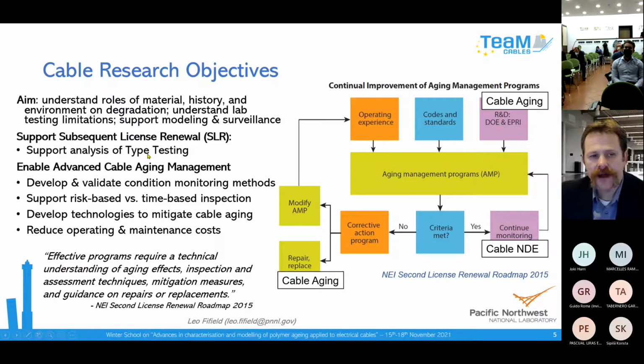Now, as I mentioned, with the license renewal, the cable aging management programs, each time there's an outage or throughout the plant's operation, select cables are tested at a time on certain frequencies, not every cable. So they pursue a strategy called type testing, where you try to find the cable that's in the most severe condition or the most susceptible to aging, and test those first, and then you can extrapolate results from similar cables to the one that you're testing.